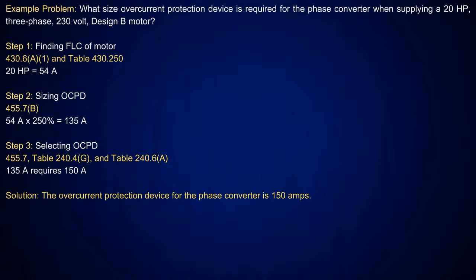Okay. And when you're sizing your overcurrent protection devices here, you have to look at this, and it's going to tell you to take that at 250%, and that'll give you 135 amps, but it's going to tell you you have to protect the conductor. So the next size overcurrent protection device above that for table 240.6A is 155 amp. Now, one of the things I like to do when I'm going through this kind of stuff like this is I like for everybody to go through and see just exactly what it says.